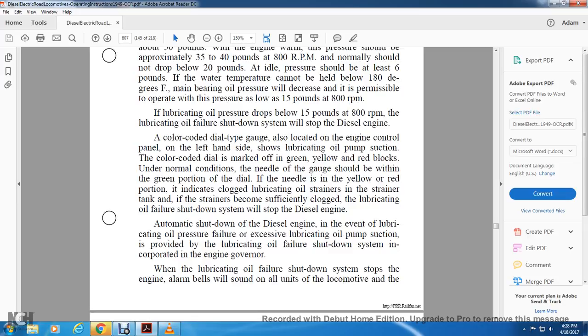Automatic shutdown of the diesel engine occurs in the event of lubricating oil pressure failure or excessive lubricating oil pump suction, and is provided with the lubricating oil failure shutdown system incorporated in the engine governor.